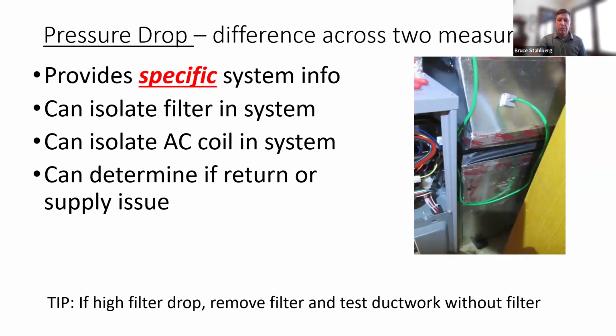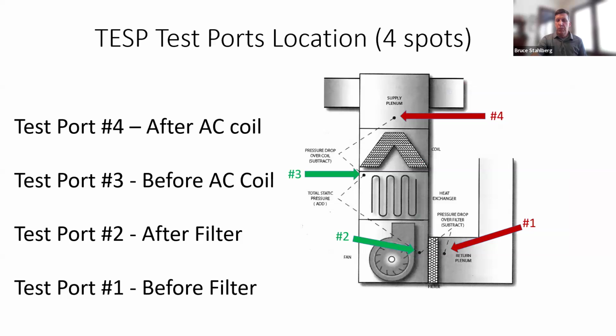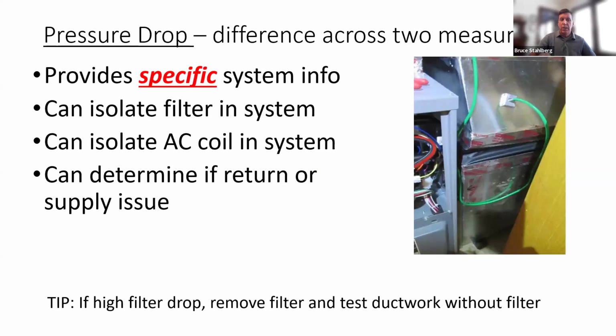Now notice I'm going to go back here. If you look at number 1 and number 2, that's 2 different ports over the filter. That will tell you how much the filter is eating up, and that's called a pressure drop. You can also do the same thing on an air conditioning coil, and it kind of gives us a way to determine whether the coil might have a problem with being plugged. So that's called a pressure drop. And the difference across 2 measurements can isolate the filter or the air conditioning coil, and it can determine if it's a return or a supply issue.